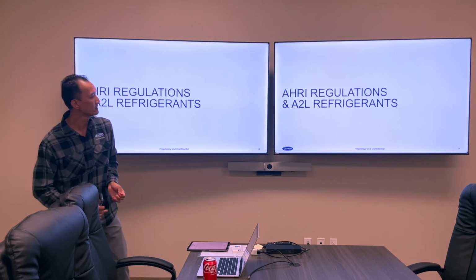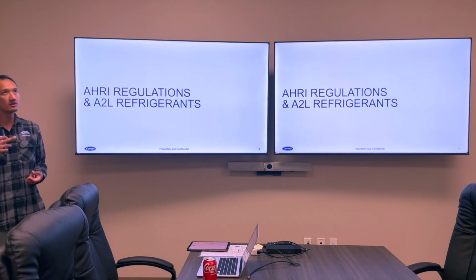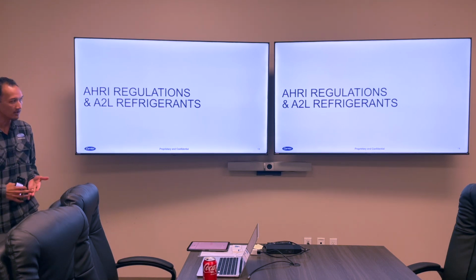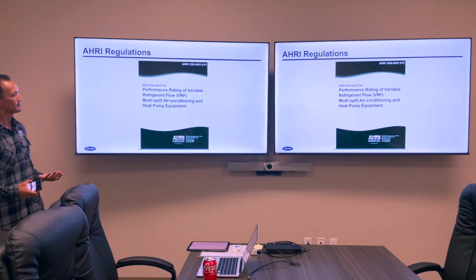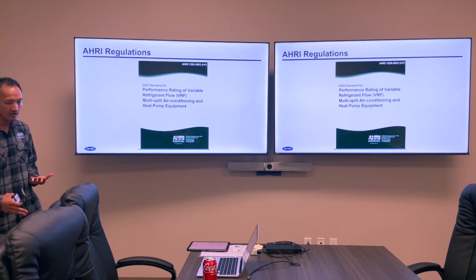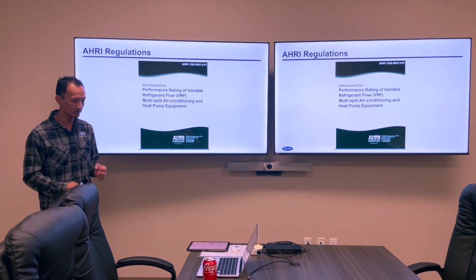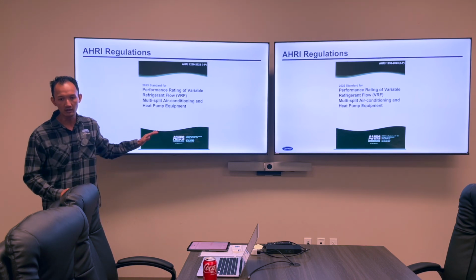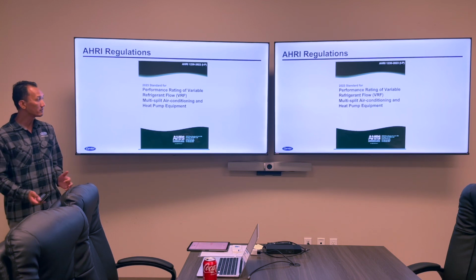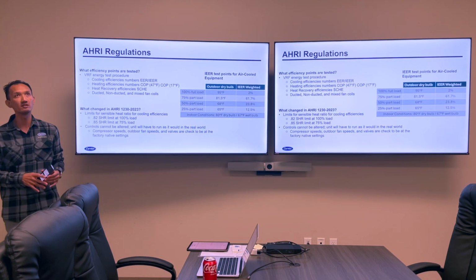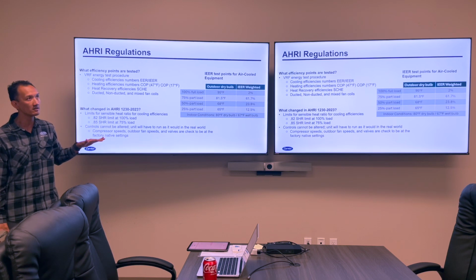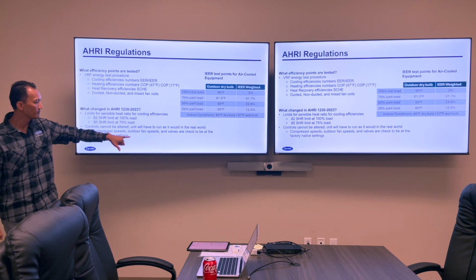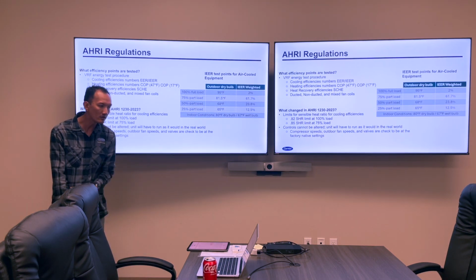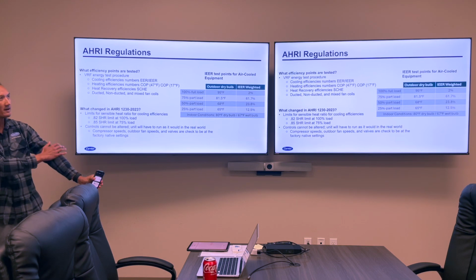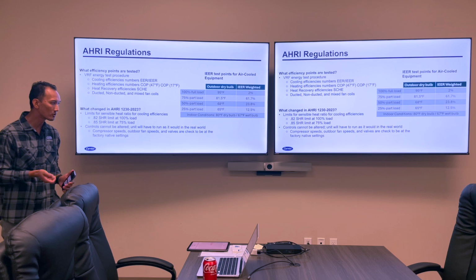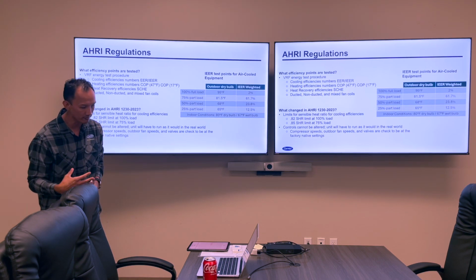All right, cool. So last section, talking about AHRI regulations, A2L refrigerants, and the new testing methods for testing VRF. So AHRI, they test all types of equipment for efficiency ratings. They updated the standard for how to test VRF systems in 2023. Basically, the way the equipment comes off the line is how it has to be tested. Controls cannot be altered. The unit will have to run as it would in the real world. And what we noticed was that some of the other manufacturers were tweaking their control algorithms, trying to eke out the best performance.